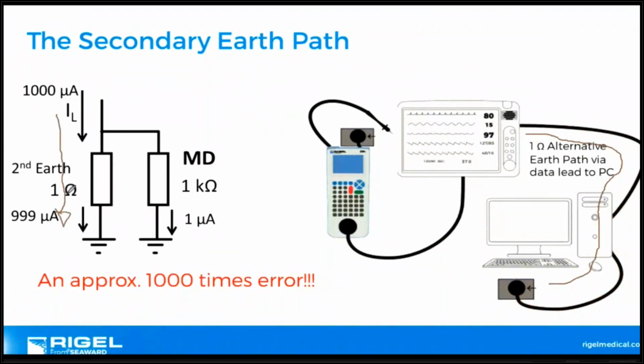and I've got an arbitrary figure there of 1 ohm. So a measuring device, which is a 1K resistor internal here to measure the current, won't measure anything, or it will measure something that is going to be deemed as safe. So if you haven't got an electrical safety analyzer that is informing you of these alternative earth paths or secondary earth paths, then you're not correctly measuring the fault currents. Commonly misunderstood concepts of electrical safety testing.